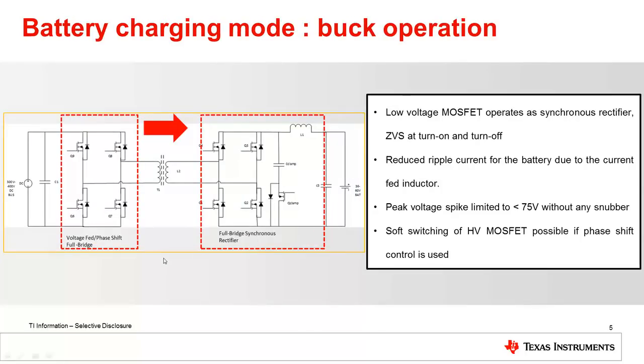In the battery charging mode, that is when drawing power from the 400 volt DC bus and charging the battery, the system works as a voltage fed or a phase shift full bridge converter. The low voltage MOSFETs operate as synchronous rectifiers and therefore achieve zero voltage switching at turn on and turn off.